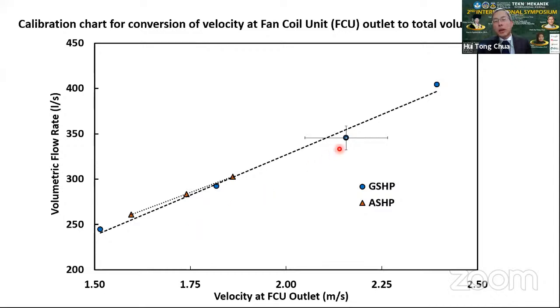You can see here that the error bar experienced quite a bit of turbulence in terms of the velocity because of the constraint of the attic size. We cannot have sufficient length to straighten out the flow. So we have to grapple with the turbulence of the air and correlate against the volumetric flow as picked up by the test hood at every diffuser. This was the tensest moment in the project, the most crucial part of getting high quality data.